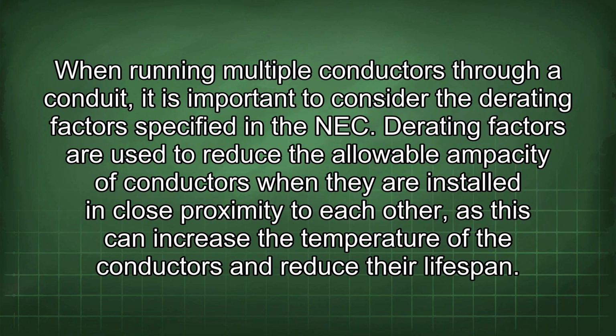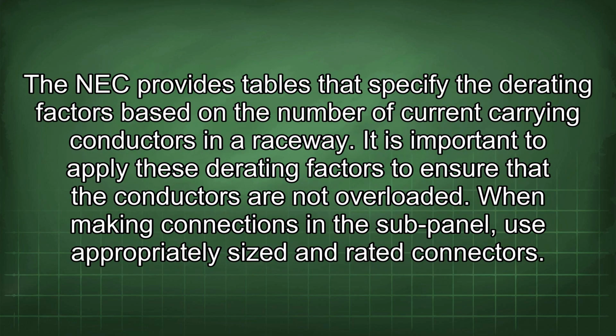When running multiple conductors through a conduit, it is important to consider the derating factors specified in the NEC. Derating factors are used to reduce the allowable ampacity of conductors when they are installed in close proximity to each other, as this can increase the temperature of the conductors and reduce their lifespan. The NEC provides tables that specify the derating factors based on the number of current-carrying conductors in a raceway. It is important to apply these derating factors to ensure that the conductors are not overloaded.